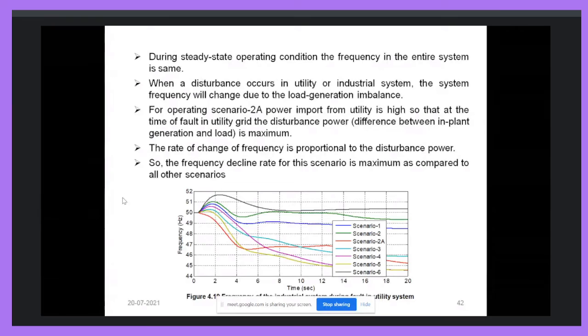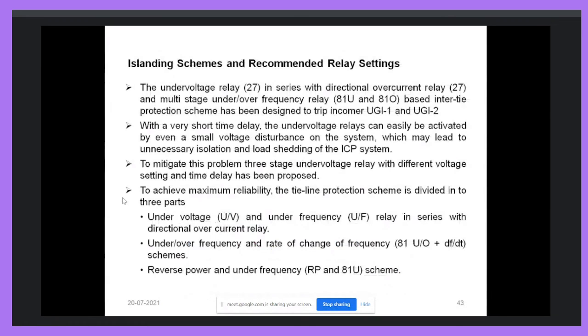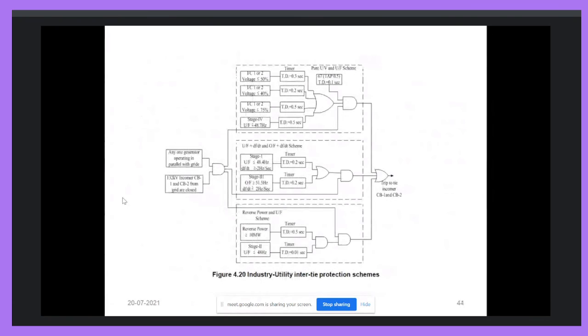Okay, so we know that if operating condition changes, the variation of parameters like frequency and voltage will change. So our protection system, our load shedding system, must operate according to the present operating condition, the pre-fault and post-fault condition of the system. So I'm not going into the detail of the islanding protection design. Here I have presented how the islanding is created.